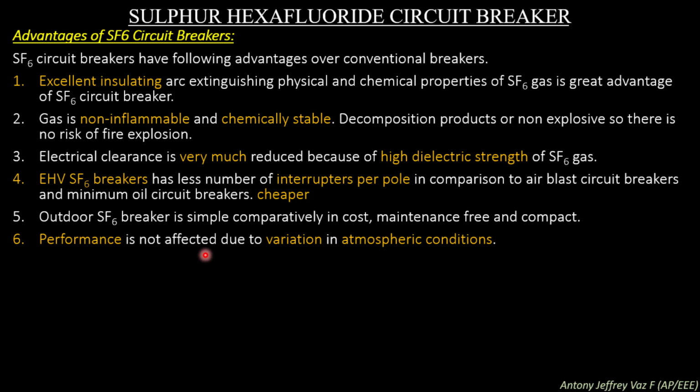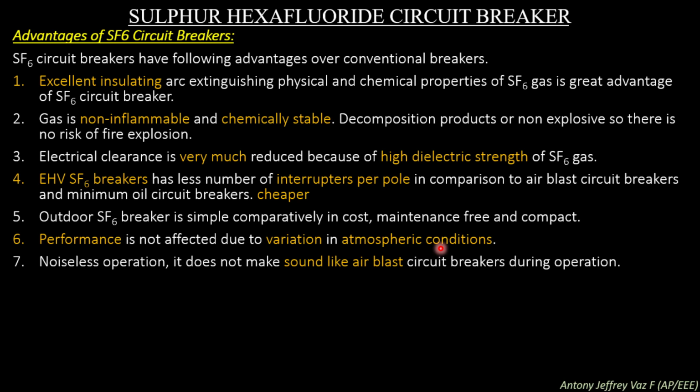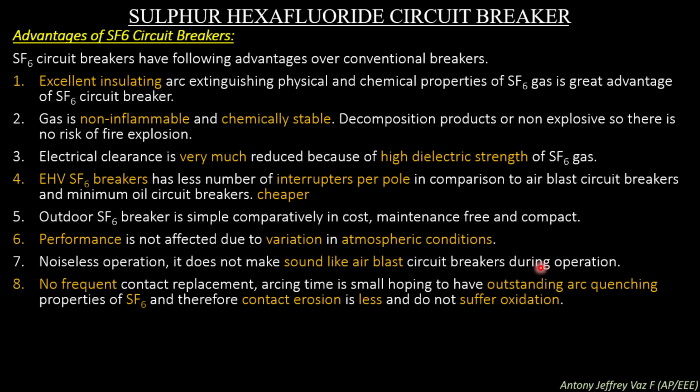Performance is not affected due to variation in atmospheric conditions. Noiseless operation: it does not make sound like an air blast circuit breaker during operation. No frequent contact replacement. Arcing time is small. Owing to the outstanding arc quenching properties of SF6, contact erosion is less and contacts do not suffer oxidation.